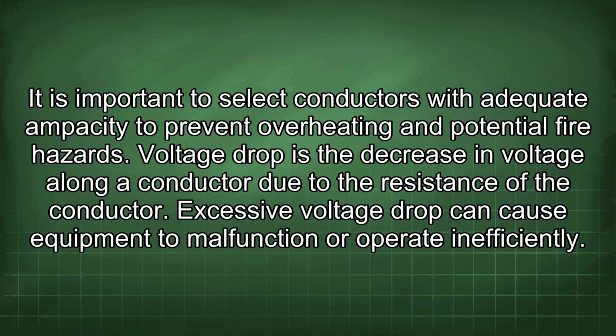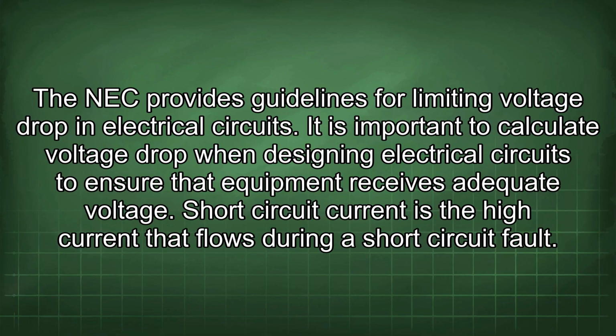Voltage drop is the decrease in voltage along a conductor due to the resistance of the conductor. Excessive voltage drop can cause equipment to malfunction or operate inefficiently. The NEC provides guidelines for limiting voltage drop in electrical circuits. It is important to calculate voltage drop when designing electrical circuits to ensure that equipment receives adequate voltage.